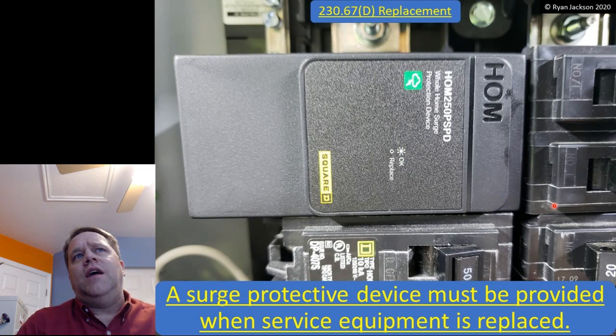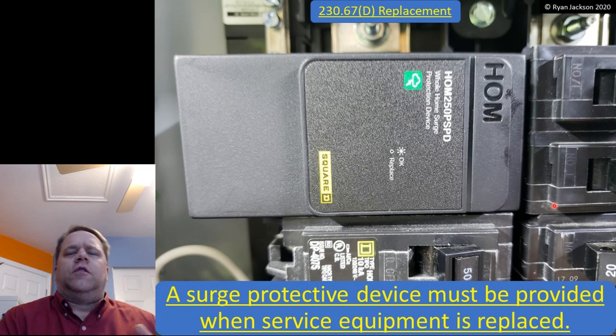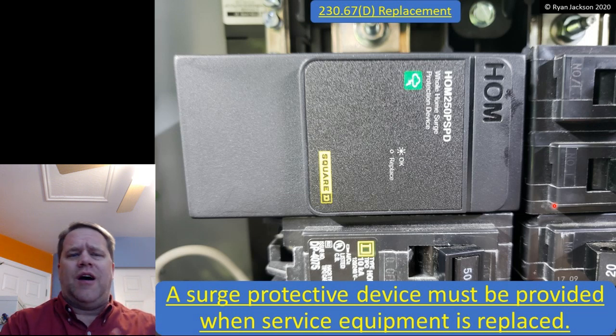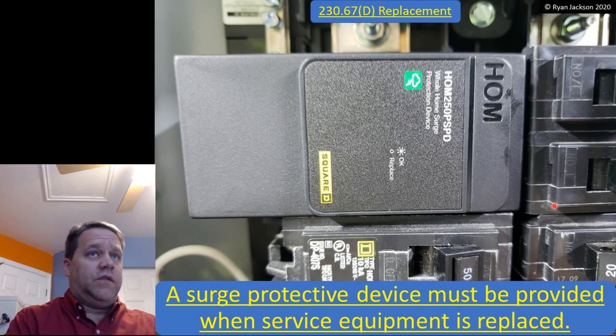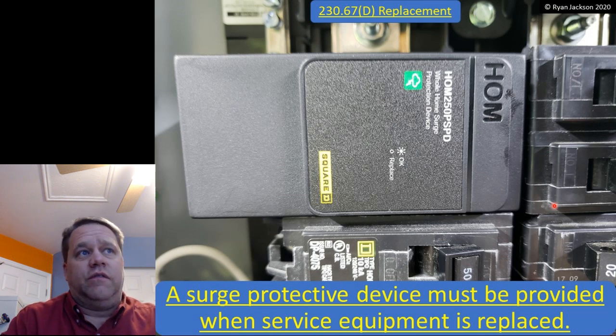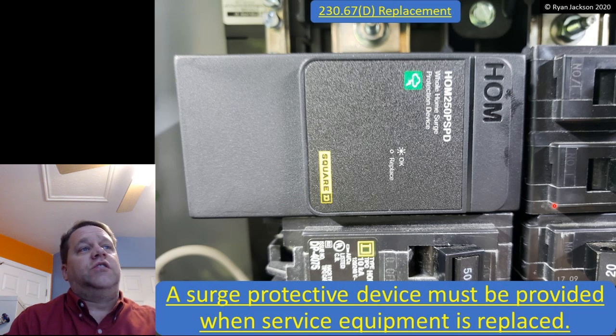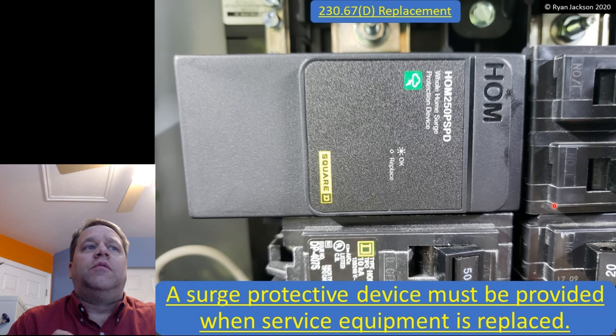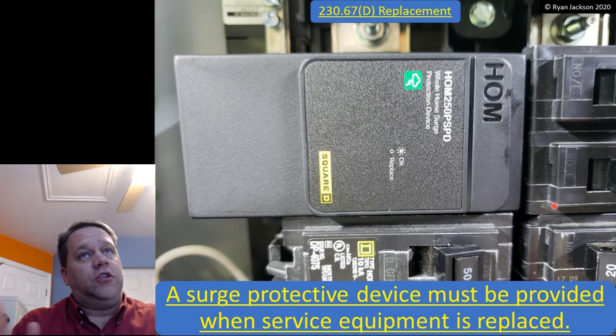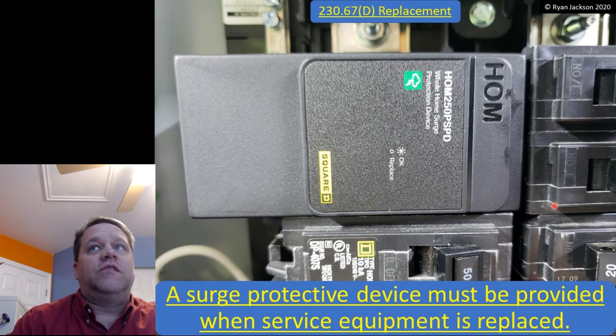You can love this rule or hate this rule, but I really like the way they approached this new subsection D, which addresses replacements. A surge protective device must also be provided when the service equipment is replaced. It's always difficult when you deal with existing situations. How much does the code apply? When does it apply? What do we have to do? Love this rule, hate this rule, the worst it can be is silent, and it's not silent. If you replace the service disconnect, you have to install a surge protective device. So this rule applies not just on new installations, but on replacements as well. I think that's probably true whether this section says it specifically, but it does avoid any sort of argument. If you're doing a service change, you've got to install a surge protective device.